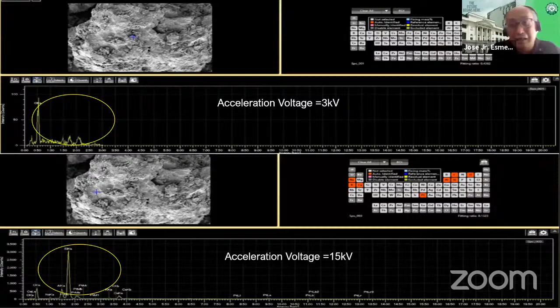So that's why, when somebody gives us a sample, I always ask them, is your sample really expendable? Because most samples for scanning electron microscopes are destructive. Once you put it inside the scanning electron microscope, it's going to be damaged. It's not going to be the same. One way or another it's going to be damaged, especially if it is a biological sample, which has to be dried, and it's damaged as well, because you're using high energy electrons in order to get information.